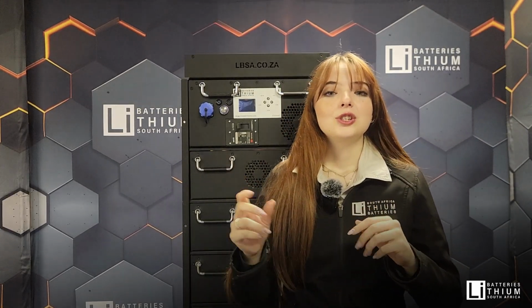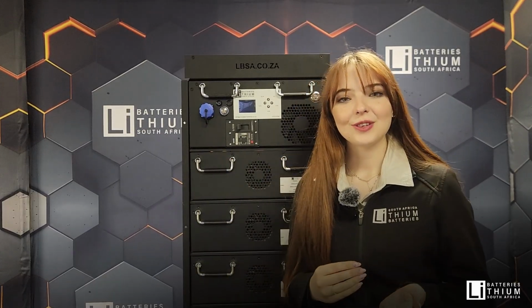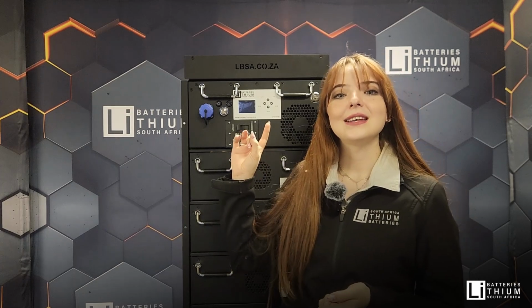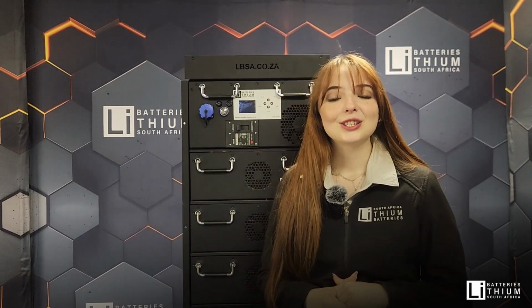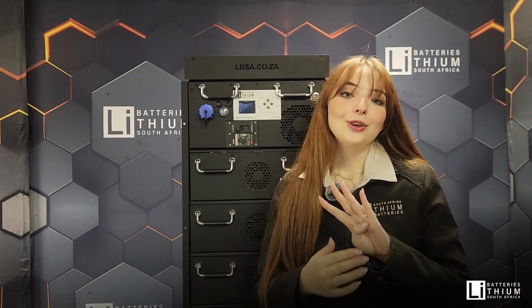Now you can connect the battery directly to a central bus bar with your solar panels and then to your inverter. So during those times, your battery will act as a sun towards the loads. We achieve this by having a time of use setting on the controller. You'll have 4 time zones and you can tell the battery when it has to discharge. This ensures that you can only use the battery during those peak times and that you will have enough capacity for those times.